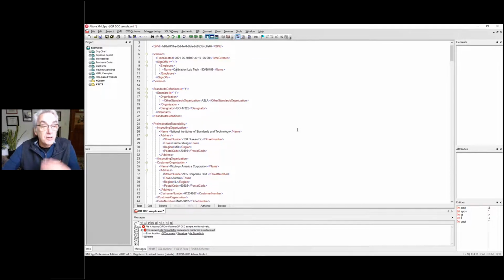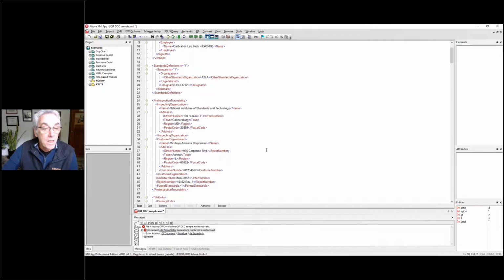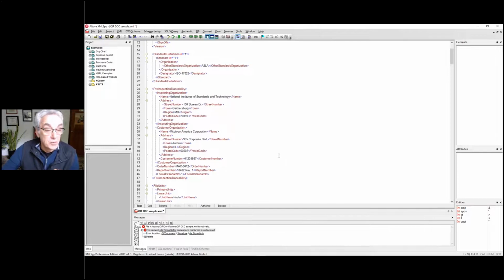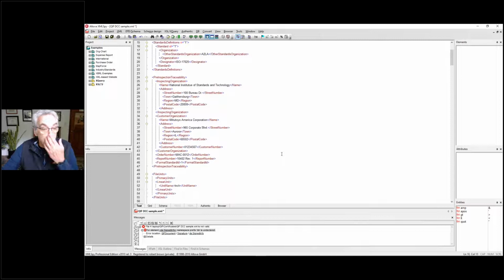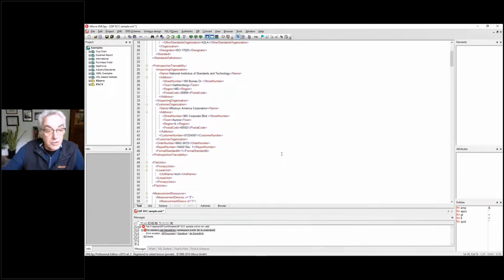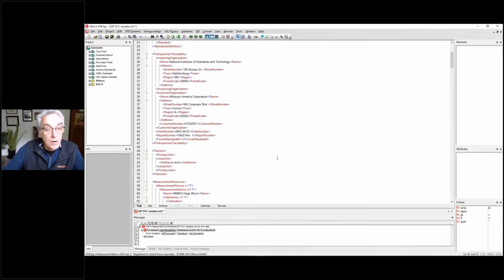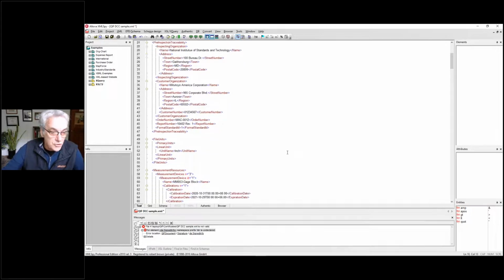We've got pre-inspection traceability with the inspecting organization, NIST, street address, postal code. Customer organization, this would be us who would receive the certificate, our name, address, our number, our organization number, order number, report number, and a formal standard ID that's referenced elsewhere. For us, our file units are inch.